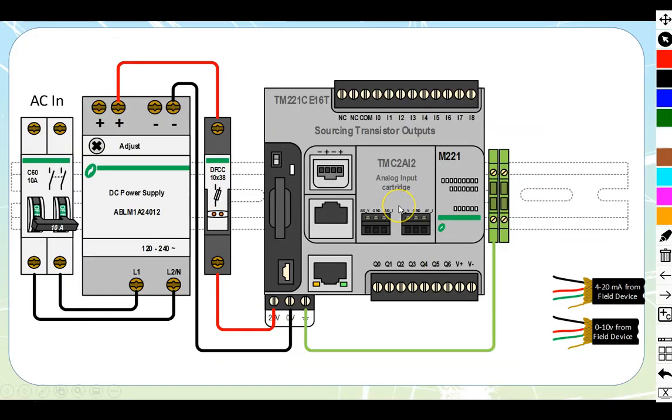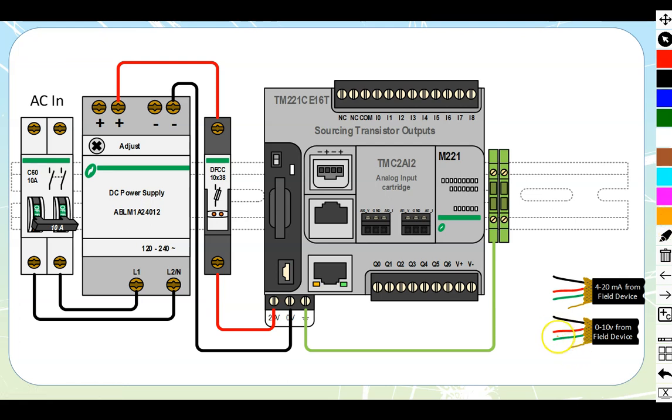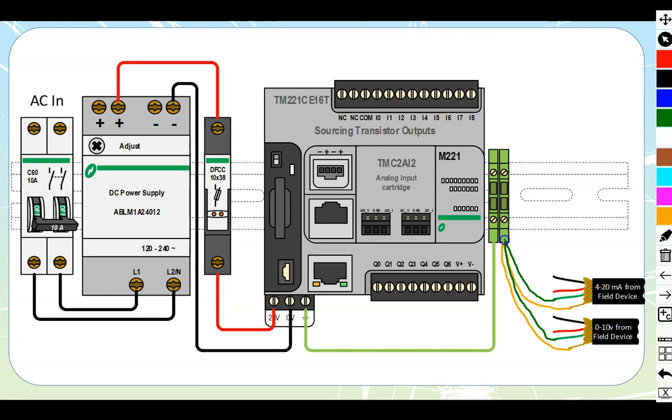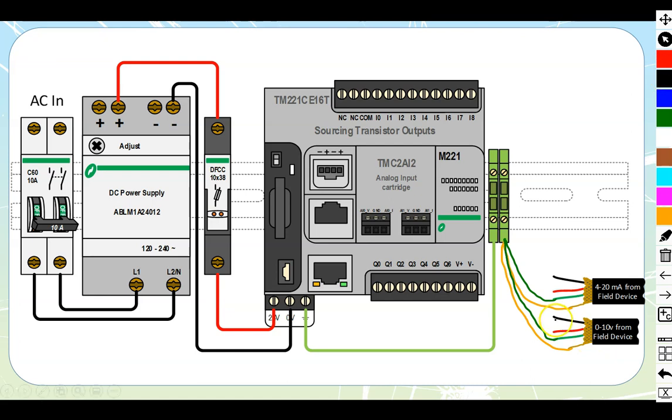Let's run in our components. First thing we're going to do is ground down all our cables. We have 4 to 20 milliamps from a field device and 0 to 10 volts from a field device. We'll take all those shields in right away and take all our grounds inside the cable if the cable has a ground in as well. The opposite end of our cable—we would isolate that shield. The shield should only be drained off at one end. You'll hear the term drain used quite commonly.